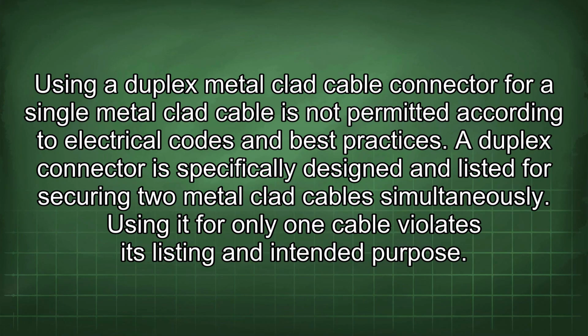Using a duplex metal-clad cable connector for a single metal-clad cable is not permitted according to electrical codes and best practices. A duplex connector is specifically designed and listed for securing two metal-clad cables simultaneously. Using it for only one cable violates its listing and intended purpose.